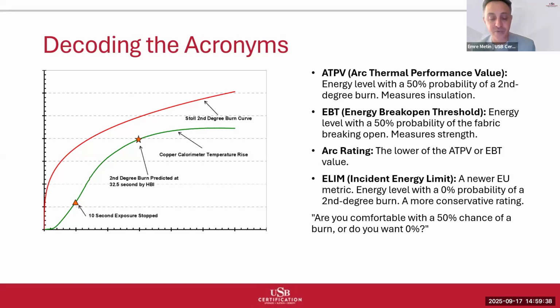ATPV, arc thermal performance value. EBT, energy break open threshold. Arc rating is always the lower value between ATPV and EBT. Why? Because protection fails when either mechanism fails. If a material has excellent thermal properties, high ATPV, but breaks open at lower energy levels, low EBT, the arc rating is limited by the break open threshold.